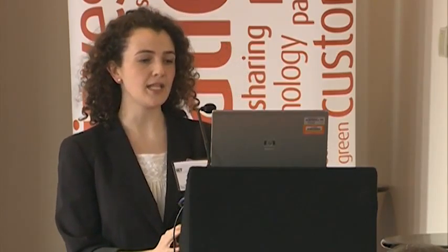So the concept of principles of access arises, and it essentially means what is the order of curtailment? So how are you going to curtail these generators? And there are many theories about this, but we essentially looked at 2 that are probably the most straightforward. The first one is last in, first out. That just essentially means on a first come, first served basis, let's curtail generators. So the first one who comes is guaranteed that if anyone comes after, the second generator will get curtailed first.